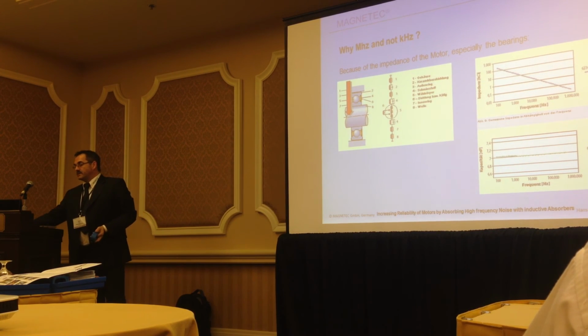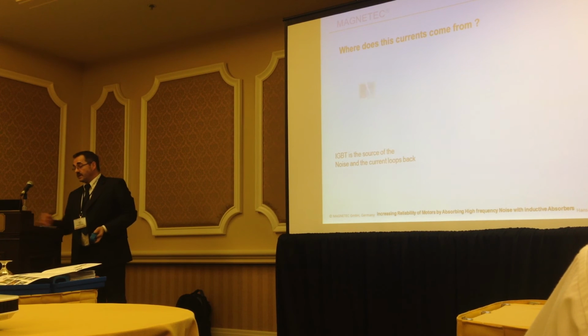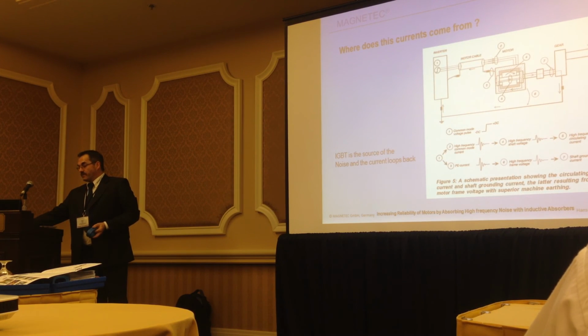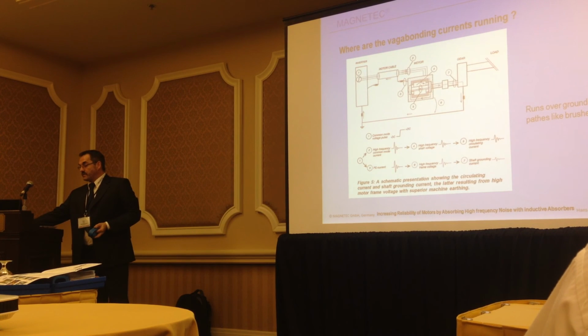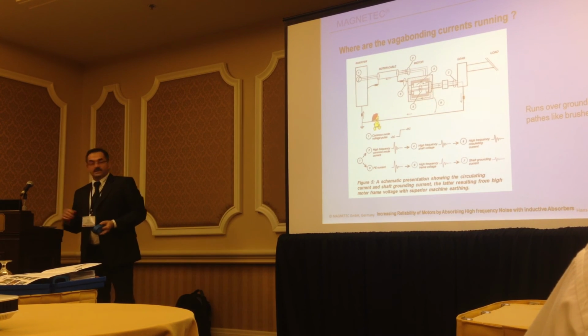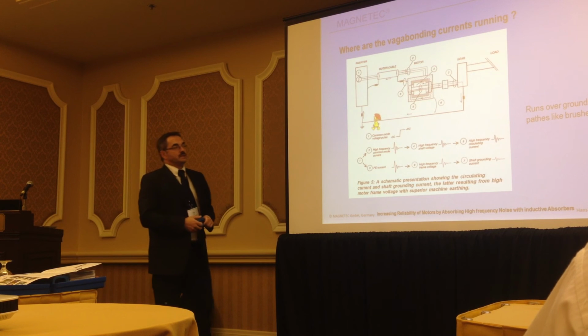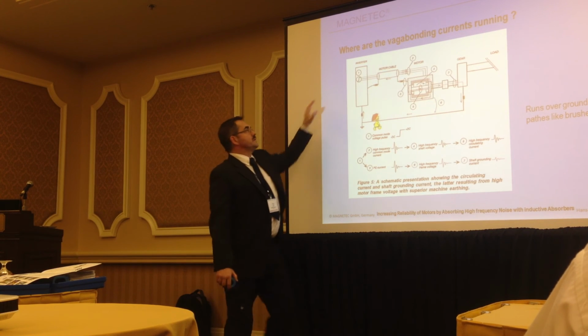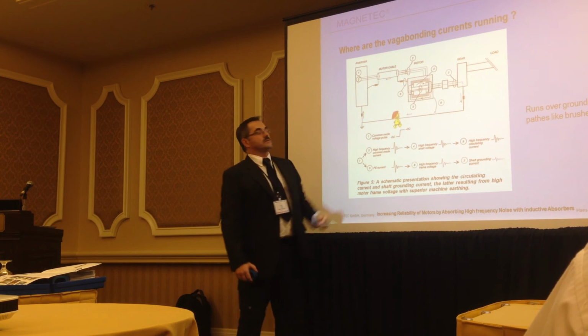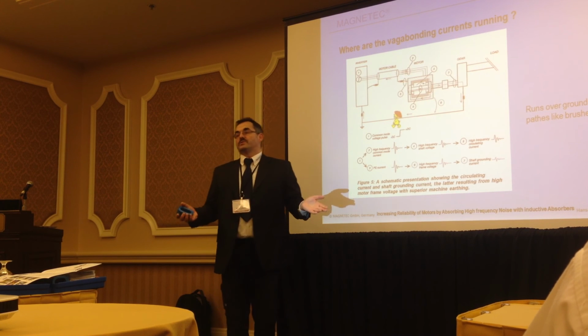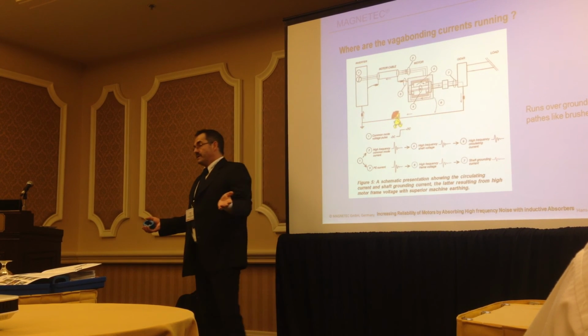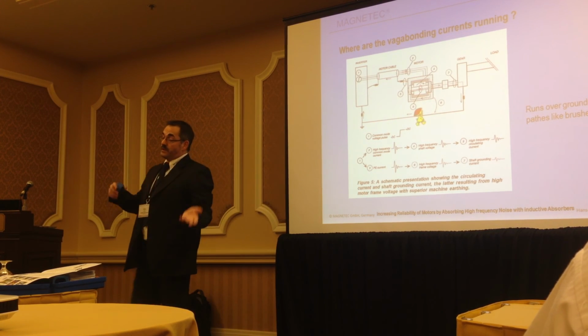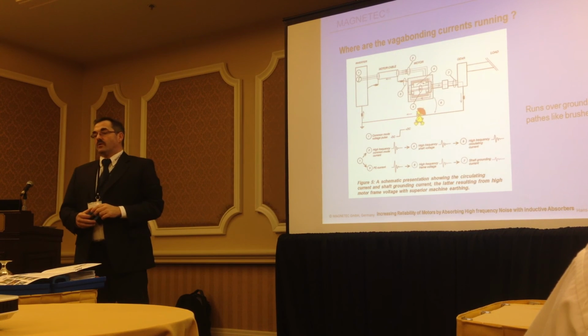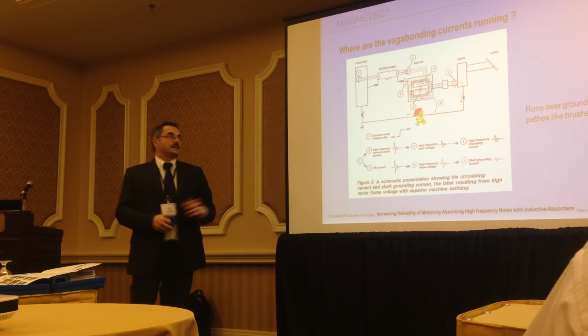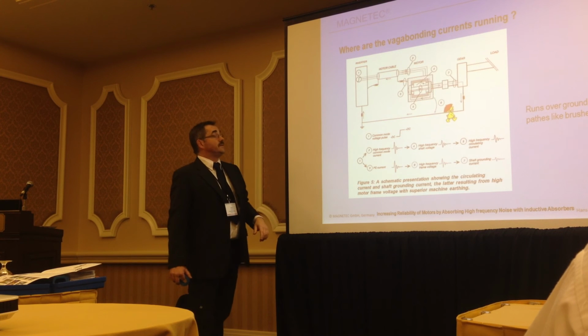And that's the target of all what you see up here. But where are these currents coming from? The source of that one, skip that one, is really the semiconductor. So it's not the grid. We are talking about the source, that's the semiconductor. And the semiconductor is normally switching, I would say, depending on the power range, in the kilohertz range. That's more, I would say, for hundreds of kilowatts, or in the 10 to 20 kilowatt range, that's in the lower frequency range.